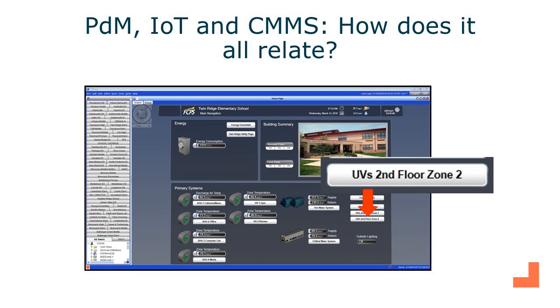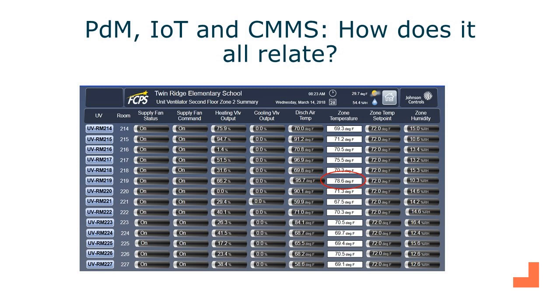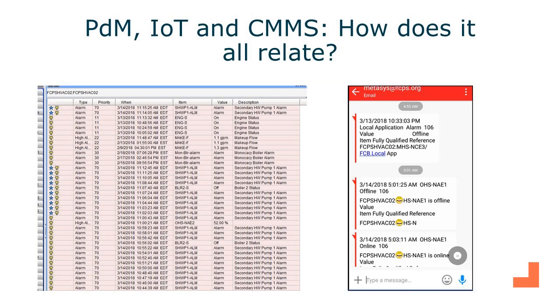If you drill down farther, like the classroom unit ventilators on the second floor, zone 2, you get a pop-up with all of those classroom unit vents where you can quickly go through the zone temperatures, the ones in white. You see one is a little out of character for what it should be—78 degrees, a little warm. You can have alarm set points configured that would show up in your alarm screen.